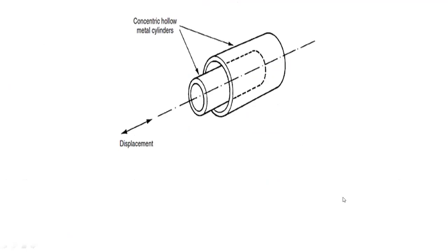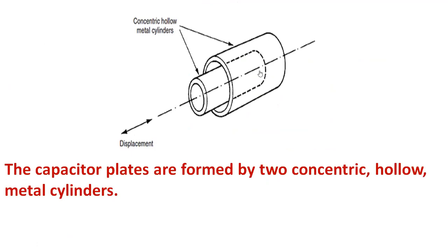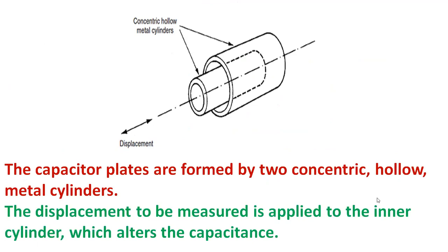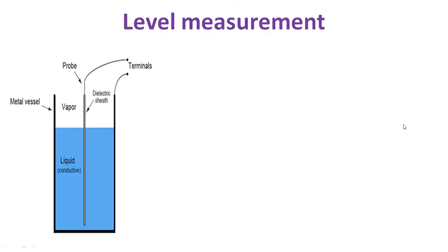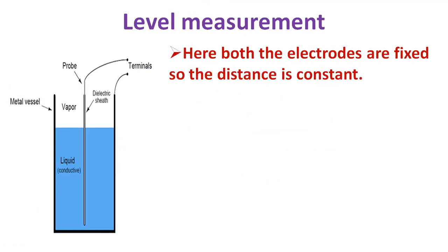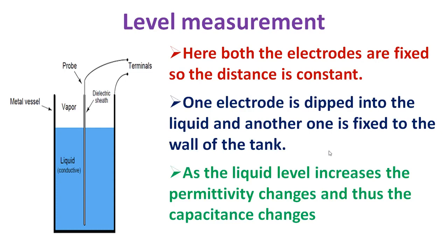The capacitor plates are also realized using two concentric hollow metal cylinders, as seen in the figure. The displacement to be measured is applied to the inner cylinder, which alters the capacitance as it moves to and fro. We also have the level measurement example. Both electrodes are fixed so the distance is constant. One electrode is dipped into the liquid and another is fixed to the wall of the tank. As the liquid level increases, the permittivity changes because the permittivity of the liquid is different from that of air. As the permittivity of the medium between the two electrodes changes, the capacitance changes — and that is how we measure the change in liquid level.